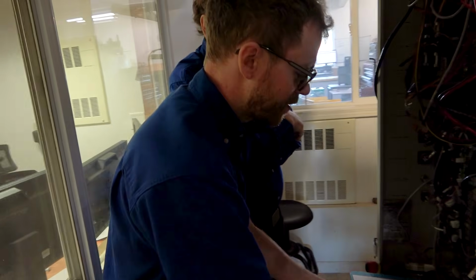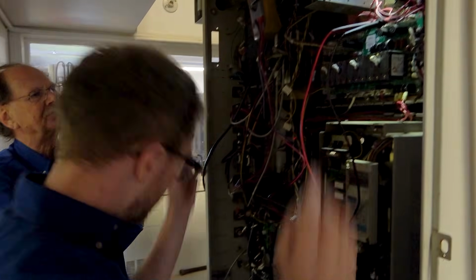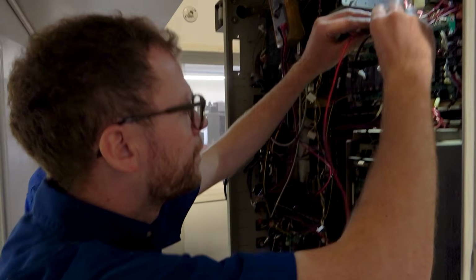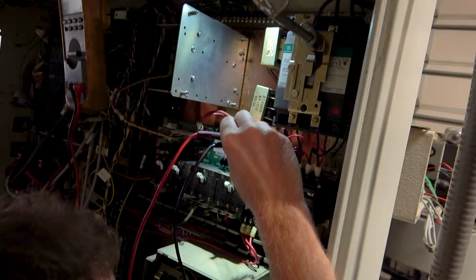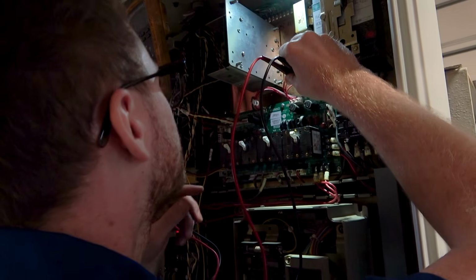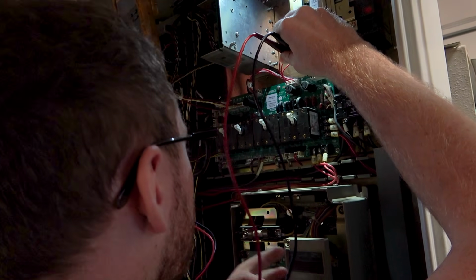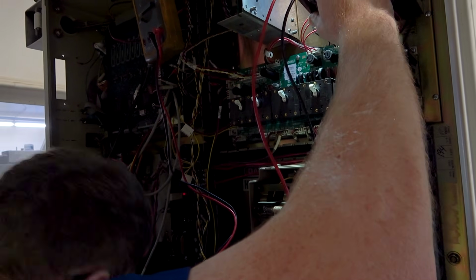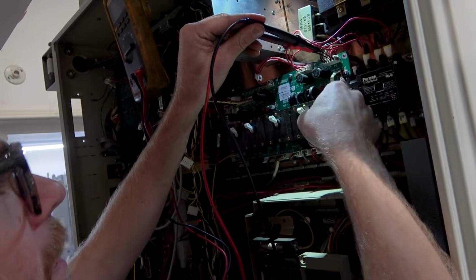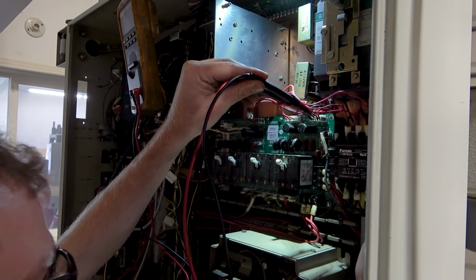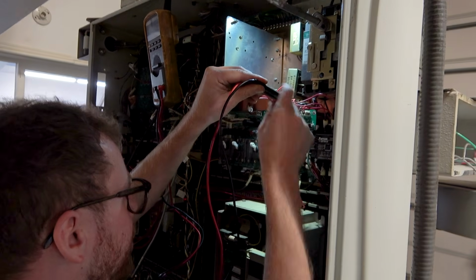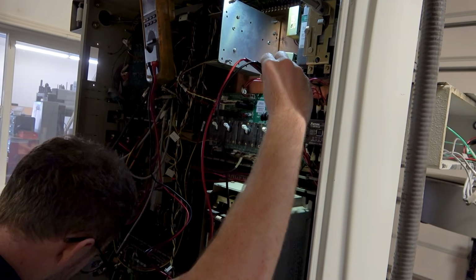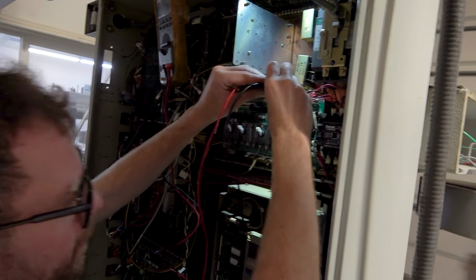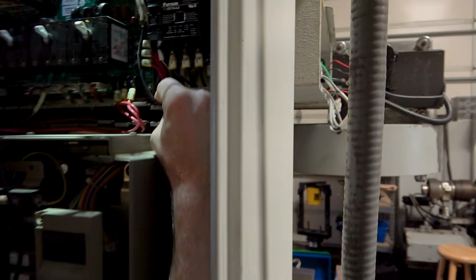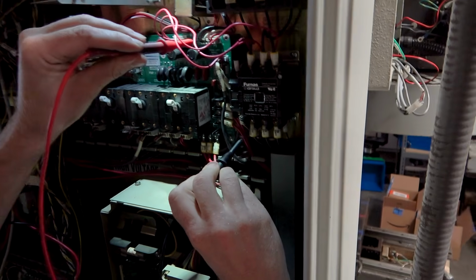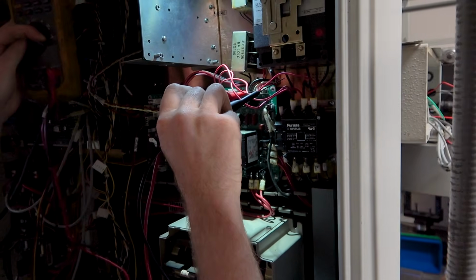Now we could even jump right to the coil of the contactor. So if I go P23, let's look here. Which one is P4, P3? You're on P5. P23 is what goes to the, looking for these wires right here, and they go up. Just measure the voltage of the contactor. Yeah, we'll go to the bottom of the contactor. Okay, 67 and 66. If I look right down in here in the bottom of this contactor, it says coil. So I'm going to measure one of these. Hope my meter auto turned off.